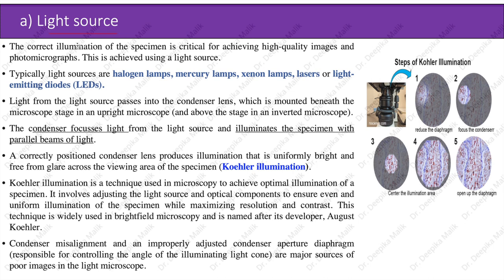Correct illumination of the specimen is critical for achieving high-quality images. Light sources typically used include halogen lamps, mercury lamps, xenon lamps, lasers, or light-emitting diodes (LEDs). Light from the source passes into the condenser lens, which is mounted beneath the stage in an upright microscope and above the stage in an inverted microscope. The condenser focuses light and illuminates the specimen with parallel beams. A correctly positioned condenser lens produces uniform illumination free from glare — also termed Köhler illumination.